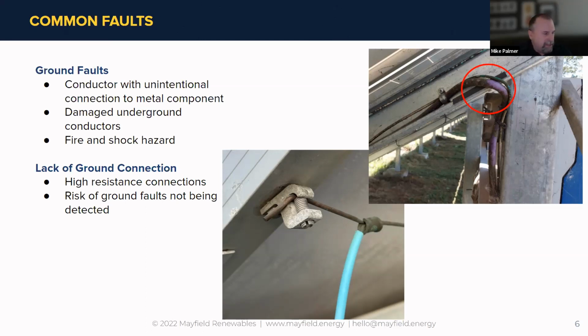We did some simple tests with the clamp-on earth tester along a whole path in a string, and found out it was open in a few places. It was easy to spot because you started with really good readings from a huge ground path going into the stanchions pressed into the earth and all the other connections. Then you find one that's open and suddenly it's not registering anything, or it reads 400 ohms where it was 5 ohms before. It really sticks out if you use that kind of tool, and we'll talk about that a little later. I won't reiterate what Ryan said, other than that dissimilar metals here will start corroding in a very quick period and be the source of problems to come.